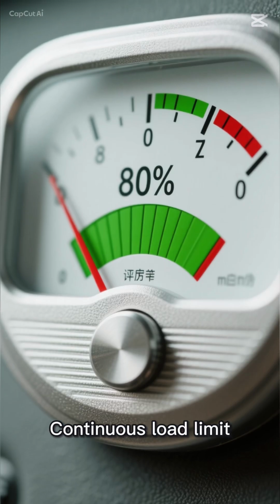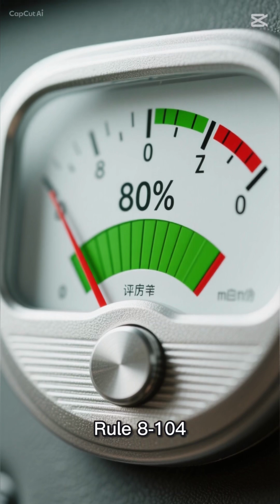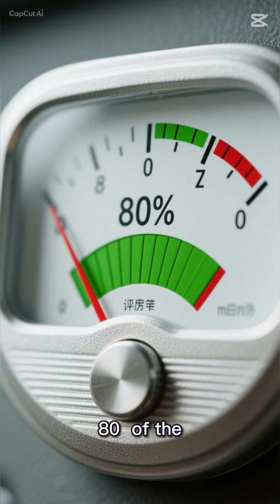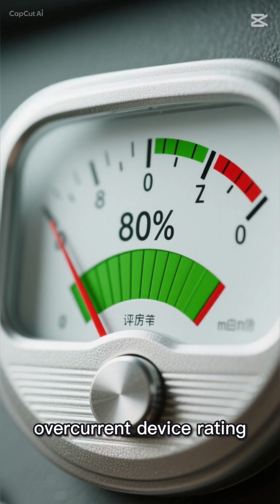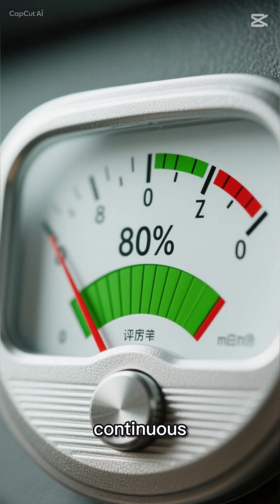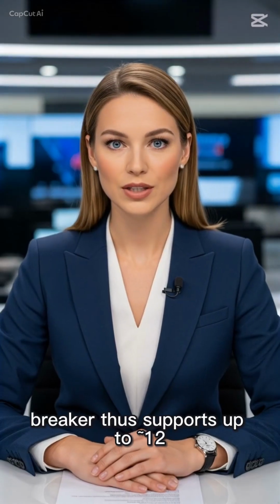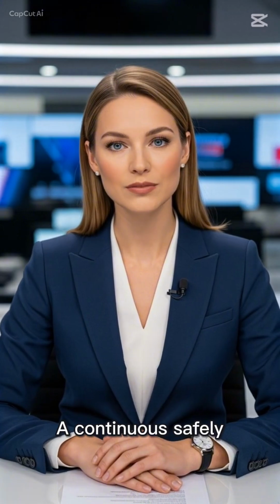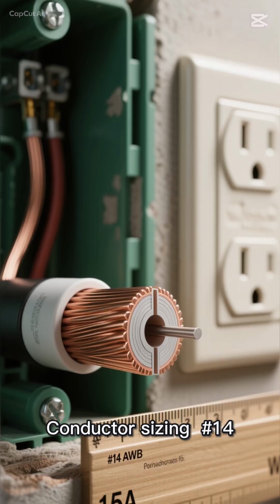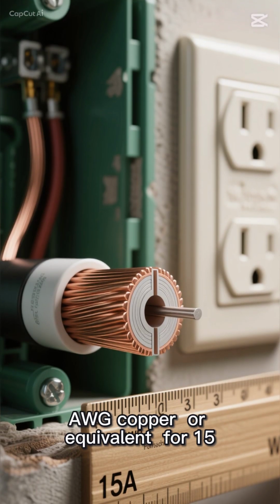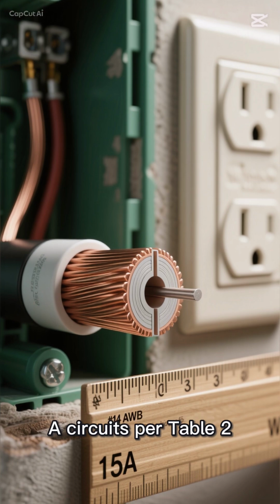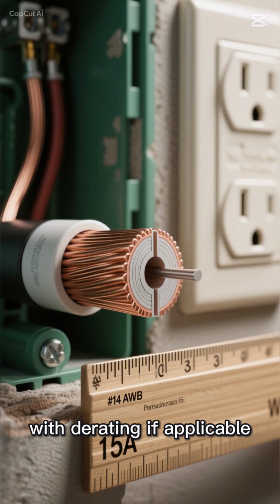Continuous load limit, Rule 8-104. Continuous loads must not exceed 80% of the overcurrent device rating, unless marked 100% continuous. A 15A breaker thus supports up to 12A continuous safely. Conductor sizing: 14 AWG copper or equivalent, for 15A circuits per Table 2 with derating if applicable.